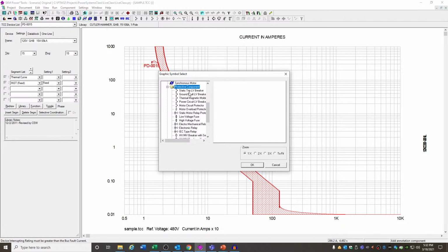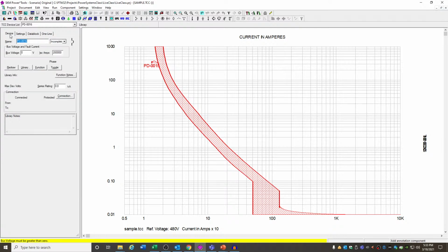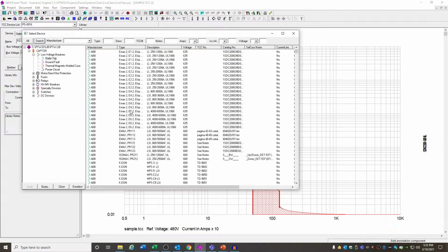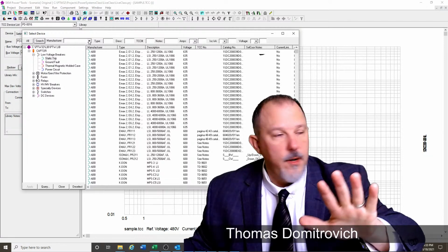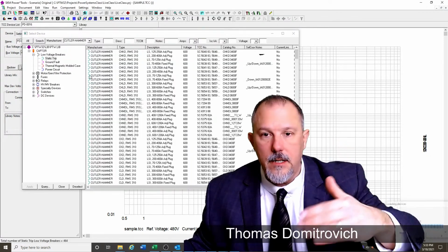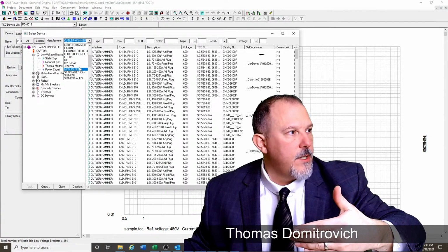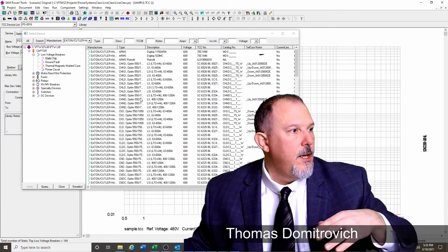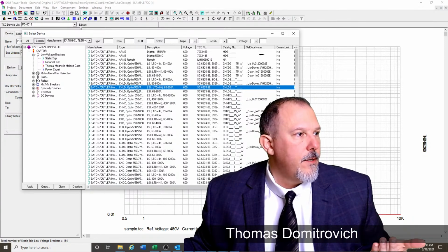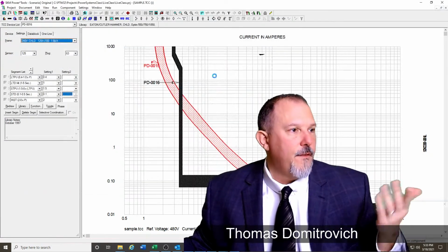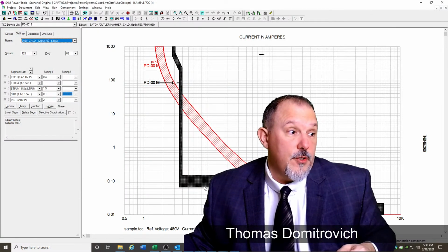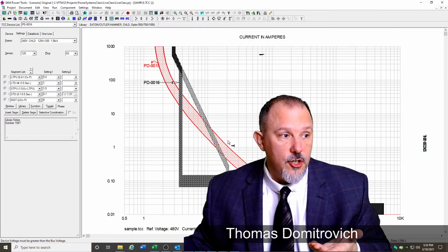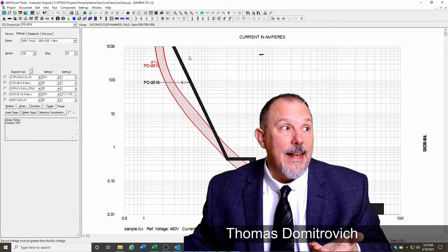I'm going to add a static trip, which means it is an electronic trip unit. I'm going to give it the same bus voltage. And now I'm going to grab, remember, for success, if you don't do this, you're going to screw everything up. You need to go in here and filter this to Eaton or Cutler Hammer. Where's the Eaton at? There's Eaton / Cutler Hammer. We'll do this one. This is a CHLD. It's an L-frame circuit breaker. This is electronic. So this helps you understand the difference between an electronic trip unit and a thermomagnetic circuit breaker.